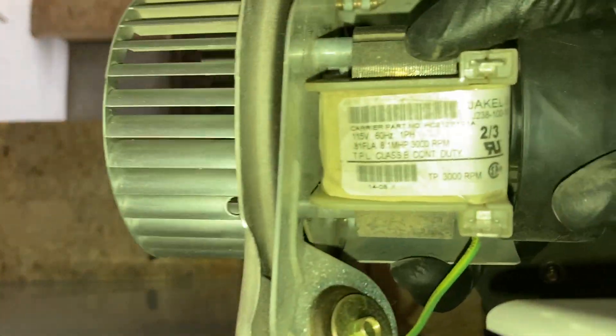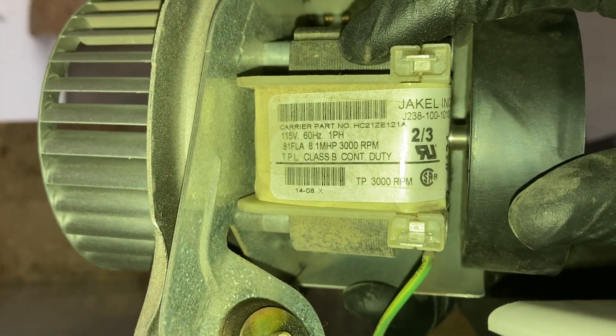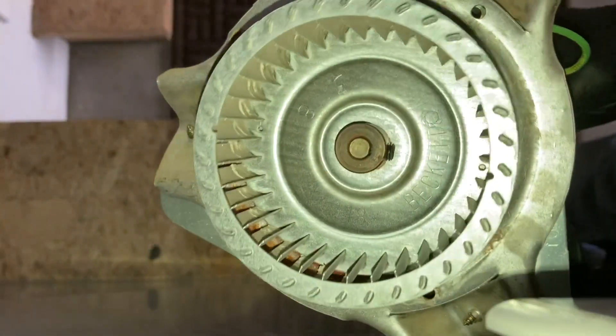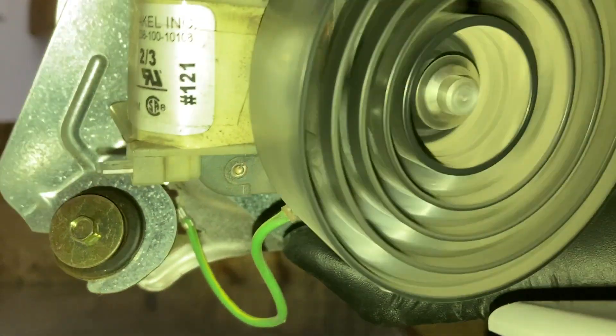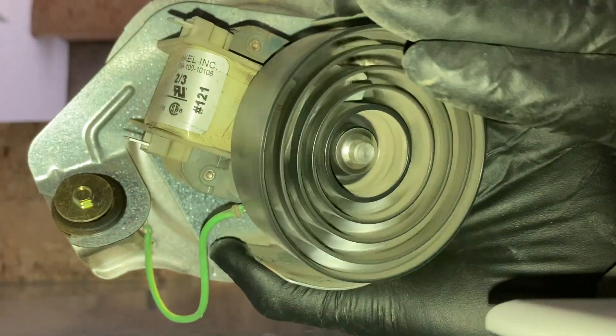This is the old inducer motor. There is the part number HC212E121A, the fan wheel. You can hear the bearings are drying out.